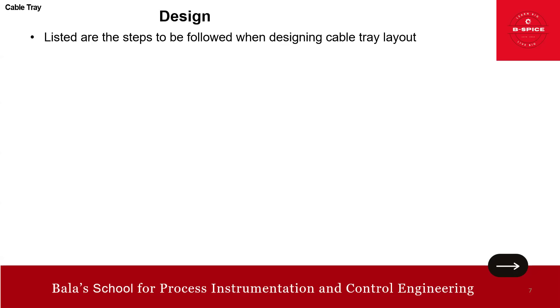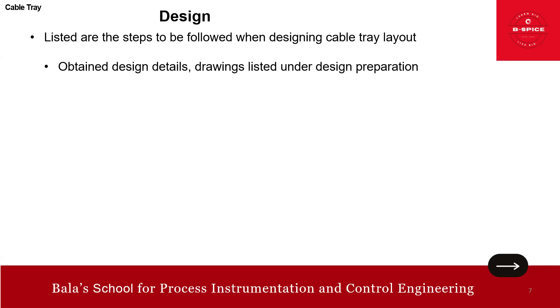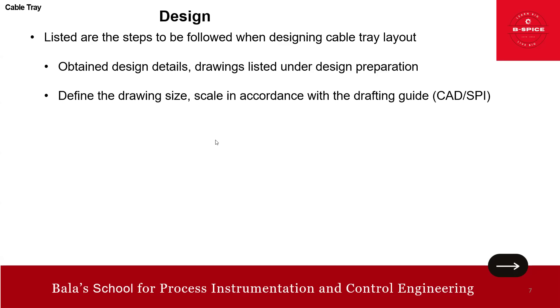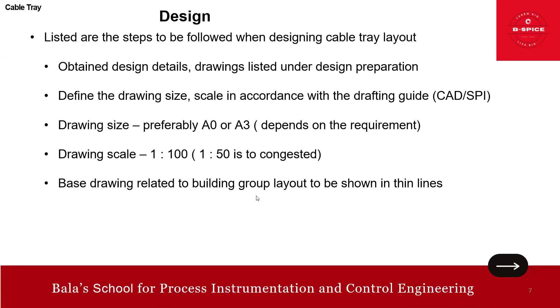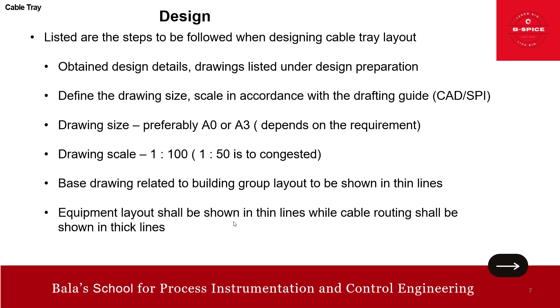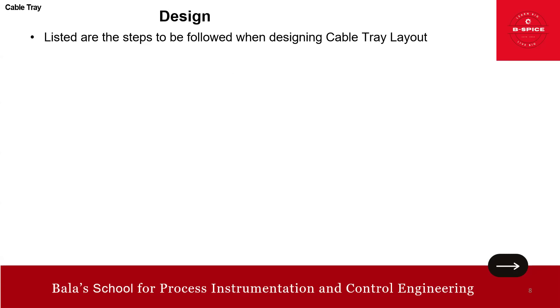For the design steps: obtain all design drawings, then determine drawing size - preferably A0 or A3 at a scale of 1:100, or 1:50 if needed. The base building group layout from civil drawings should be shown in thin lines. Equipment layout should also be shown in thin lines, while cable routing shall be shown in thick lines. This is because the cable tray is the subject of this drawing and should be predominantly visible.